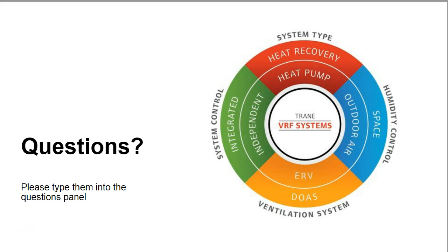Okay, so Sai, the first question is, let's say I want to add equipment to the system later on. Can I do that without impacting the rest of my design? That is a great question. Most VRF system manufacturers have the ability to let you operate systems with only 50% of the outdoor unit's capacity. A big benefit of doing this is that, let's say a different space of your building is getting zoned out later on. You can come back to your VRF branch circuit controller if you're using heat recovery, and add on to the additional ports on your branch controller.